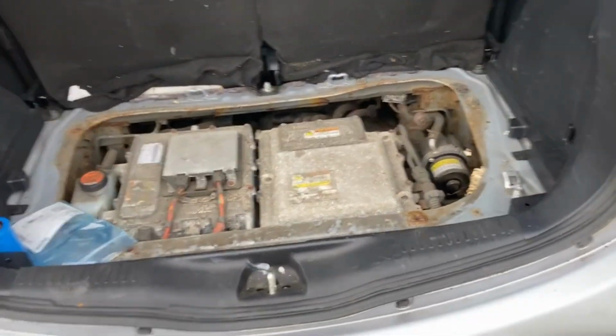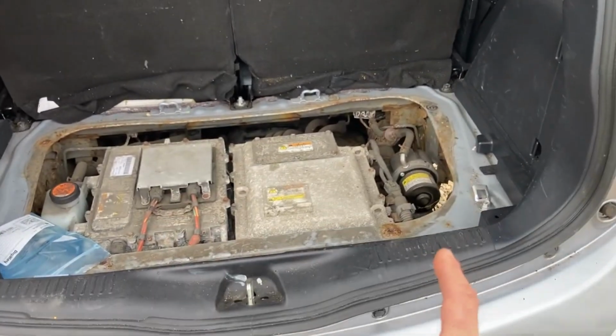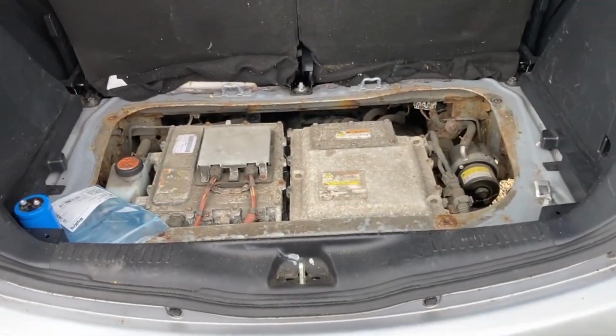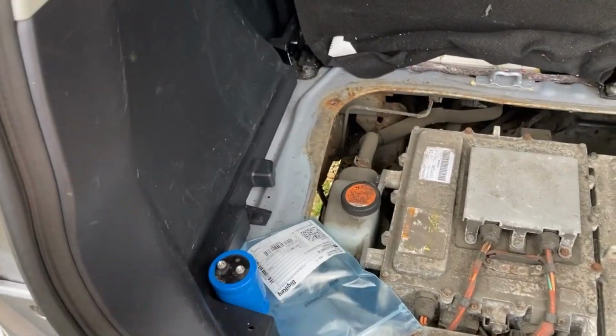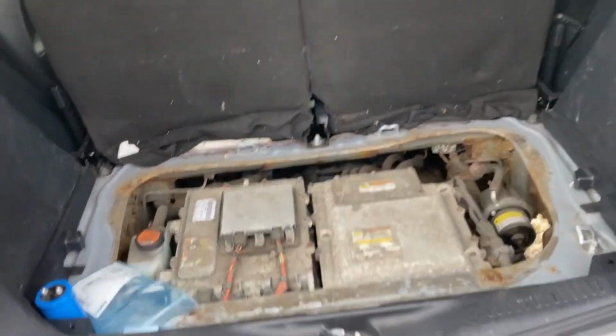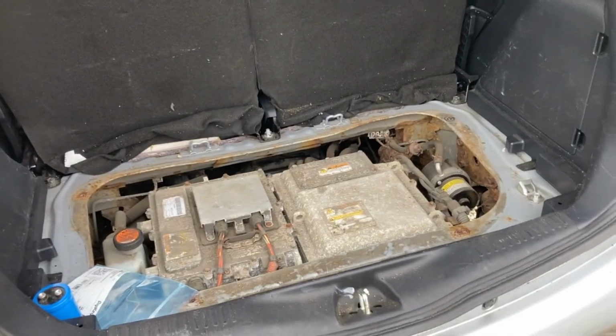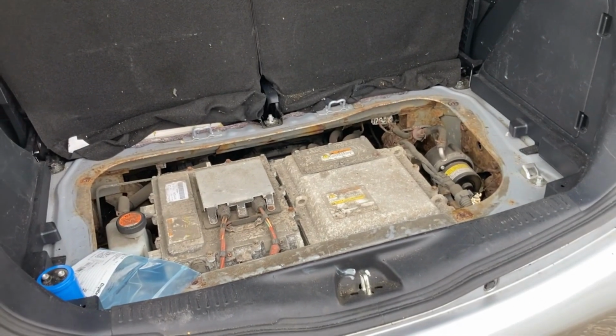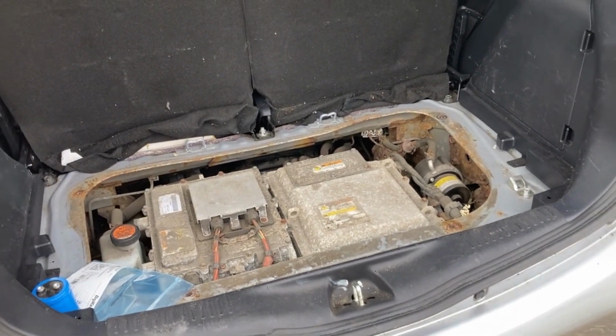If we just had two relays, one on positive and one on negative, and turned them both on, we'd get a spark every time. The spark would be big because the capacitor is big, and that would mean those contactors would last about 5 minutes because they'd get pitted and weld themselves closed.